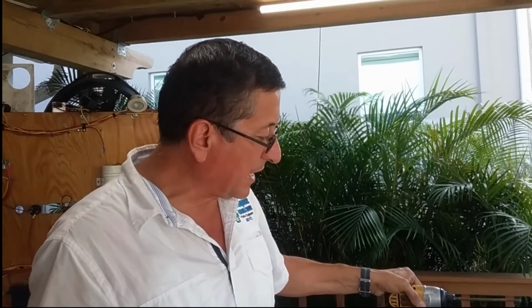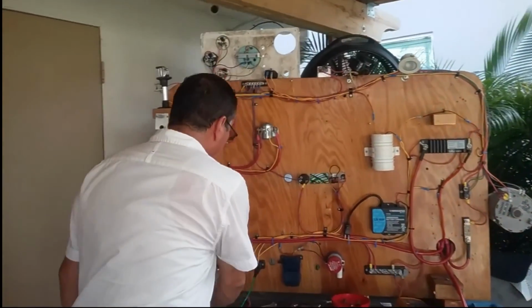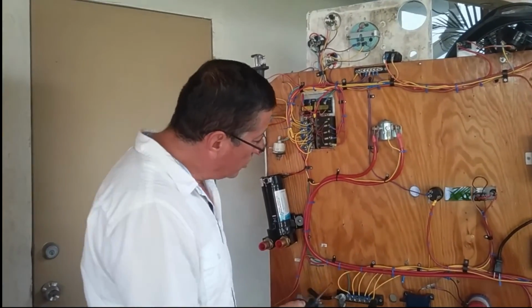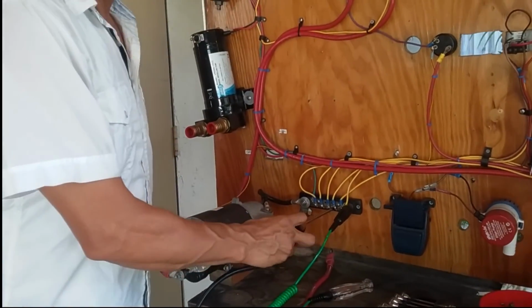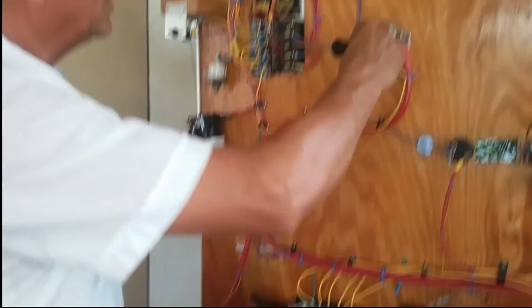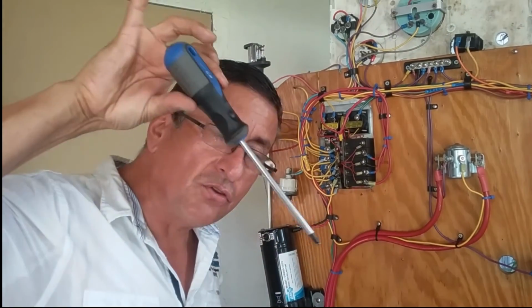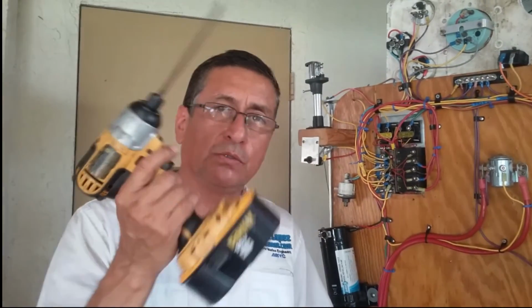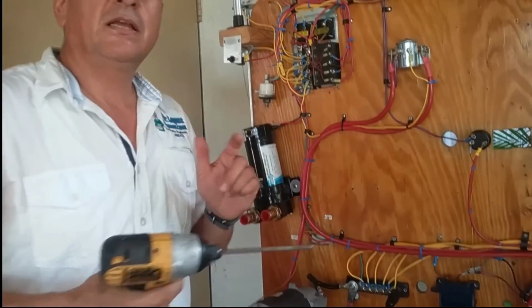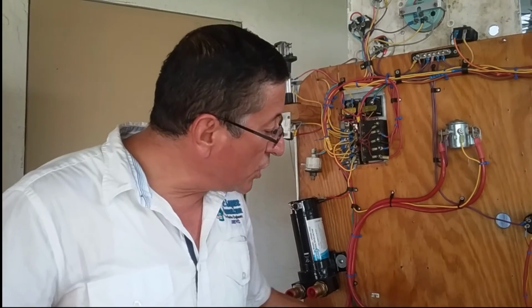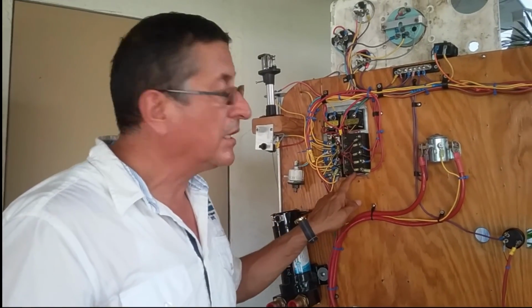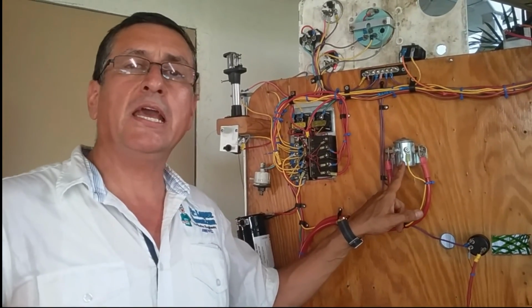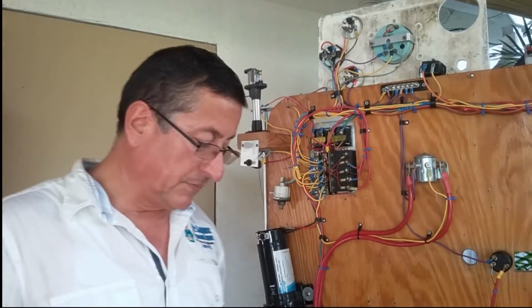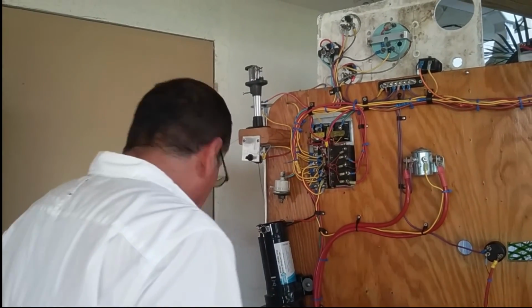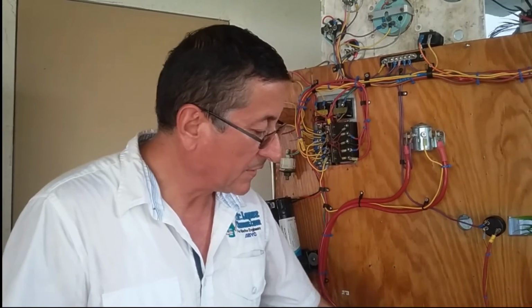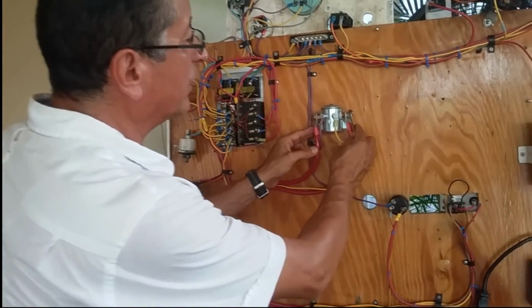Another important tool that I recommend is the screwdriver. Use a screwdriver, a hand screwdriver, in order to loosen and tighten the terminals on breakers. Never use impact tools like this. If you try to use that one, you damage the head of the screw, and you destroy the plastic on the terminal, or you destroy the breaker, or you destroy the relay. Never use impact tools. Exactly the same when you try to tighten terminals on the relays.